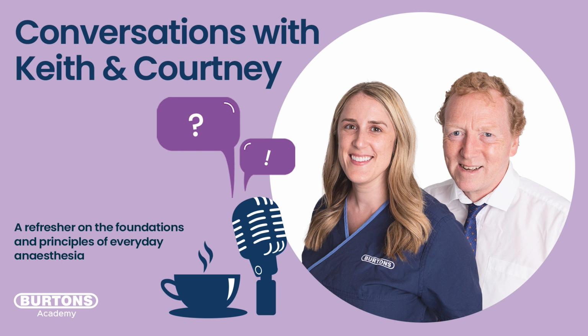I think what we want to do now is zero it, which is a fairly simple procedure. We're going to close that port off to the art line to the patient. That exposes the port, which is typically an open, empty port. We're just going to go to the monitor, normally a couple of clicks, go into the IBP menu. There'll be a zero IBP, and you click on that, and it goes beep beep, or it says 00, or it says calibration complete, or whatever the terminology is to indicate your zero has been done.